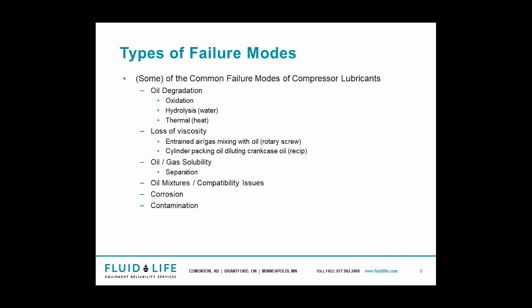You're going to have some different types of failure modes when it comes to compressor lubricants. You're going to have your oil degradation, loss of viscosity, oil and gas solubility, oil mixture compatibility issues, corrosion issues, and contamination issues.